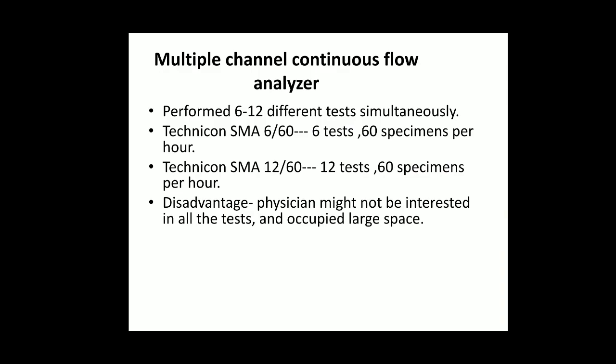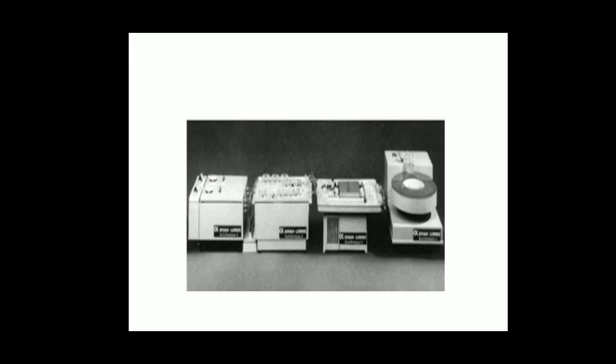Next, the multiple-channel continuous flow analyzer. Here, 6 to 12 tests can be performed. The Technicon company introduced two models: SMA 6/60, which does 6 tests on 60 specimens per hour, and SMA 12/60. The main disadvantage is that whatever sample you keep, all 6 or 12 tests will be done — but all these tests may not be required, and the physician may not be interested in all parameters. This is the main disadvantage.